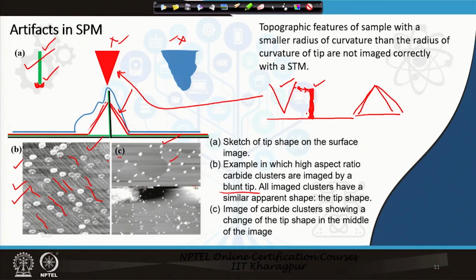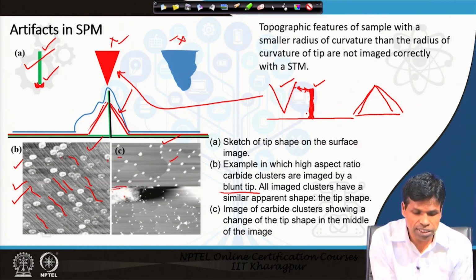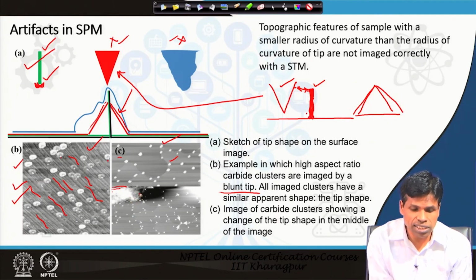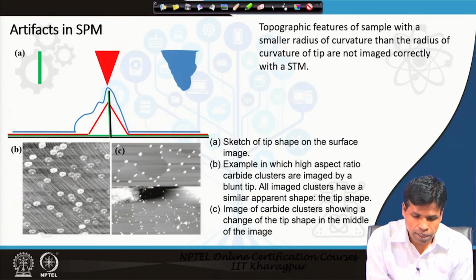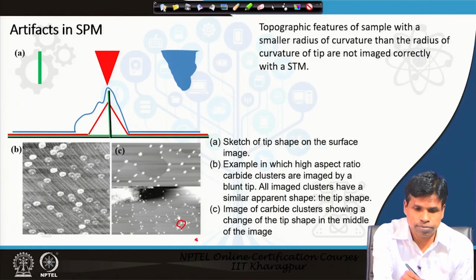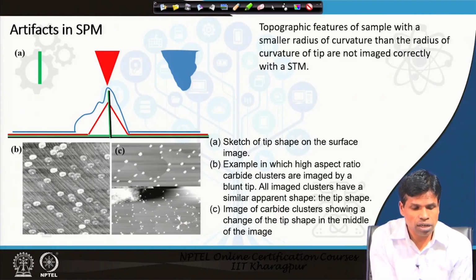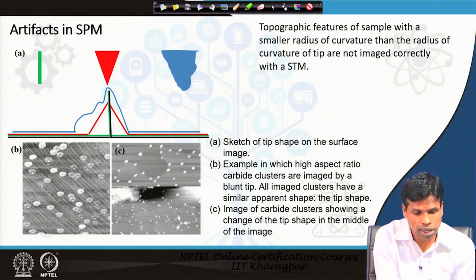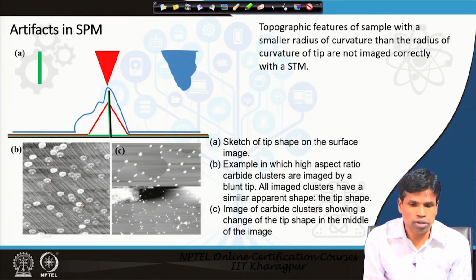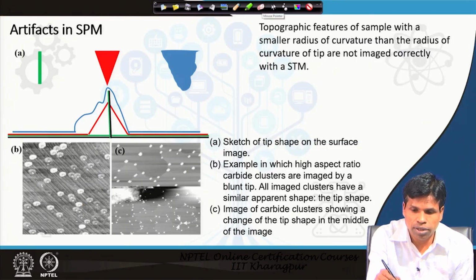Here it is larger, and during the scanning we see that in some places the tip touches the sample. There is a contact between the tip and sample, and thereby a change in the tip shape. When the tip scratches the sample surface, the tip shape changes, and that is what happened. After the tip shape changes, you see completely different types of features, and this is again not correct, because some of the particles appear as triangular or something like three dots. So, those are not correct; this is due to artifacts. If these types of features of similar shape are seen throughout the sample, with elongated features etc., this indicates artifacts of the tip providing a wrong image.